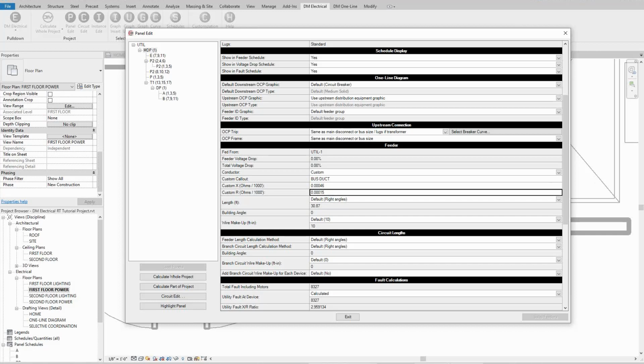You also could use it for a one-off existing circuit where you've got one circuit that's a specific size in an existing building and you don't want to go adjust your customization for it. You can just type in what it is, put in the impedances. This also allows you to do multiple parallel runs of conductors in a single conduit. The software doesn't have an option for that by default. If you're doing parallel runs, we assume you want separate conduits for them.